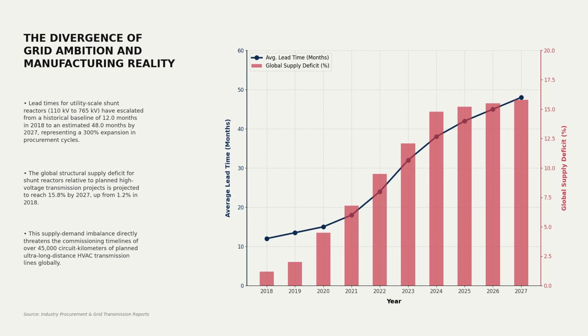But grid expansion plans have decoupled from manufacturing capacity. Lead times for utility-scale shunt reactors have quadrupled since 2018, rising from 12 months to 48 months. The structural supply deficit is projected to reach 15.8% by 2027. This bottleneck directly threatens the commissioning of over 45,000 circuit kilometers of planned transmission lines.